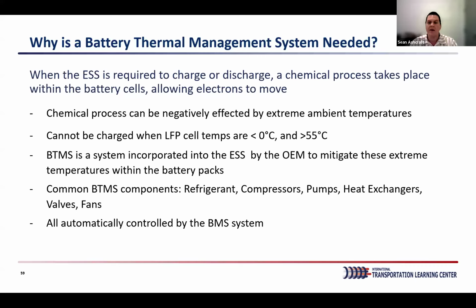For example, with the lithium iron phosphate chemistry, you cannot charge the bus when temperatures are less than 0 degrees centigrade or hotter than 55 degrees C. The BMS incorporates a thermal management system into the energy storage system, designed by the OEM, to mitigate these extreme temperatures within the battery packs. Common BTMS components include refrigerant, compressors, pumps, heat exchangers, valves, and fans, and this BTMS system is all automatically controlled by the BMS. It doesn't involve any operator interaction.